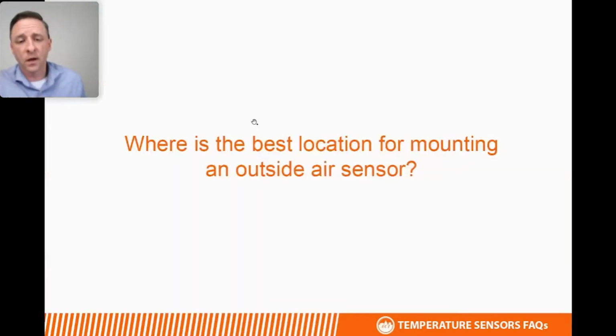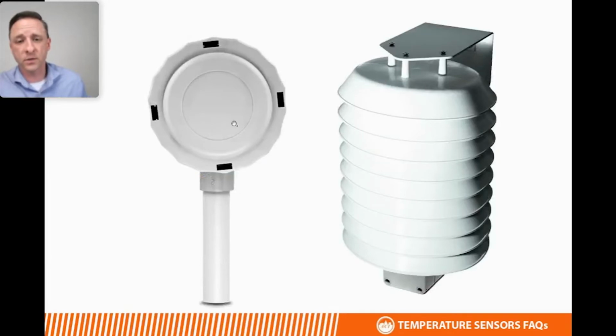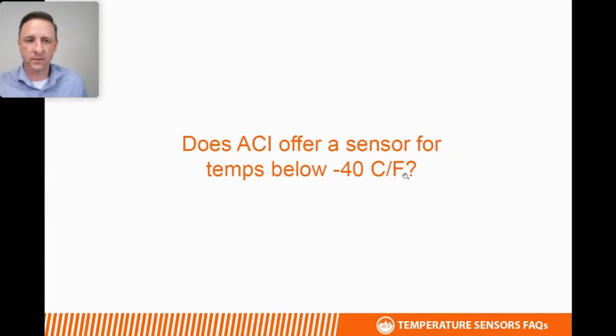For outside air sensors, the common question is, where's the best location for mounting an outside air sensor? We recommend those be mounted on the north side of a building and/or under an eave, or anywhere out of direct sunlight. Direct sunlight can cause it to self-heat and give an inaccurate reading. For those applications where there's no other location but in direct sunlight, we offer a sun shield option, which you see on the right-hand side of the screen. That is a large enclosure that radiates the heat away from the sensing element to allow for an accurate reading in direct sunlight. The probe extends up from the bottom into the middle of these plates to keep any direct sunlight or direct heat away from the sensing element.